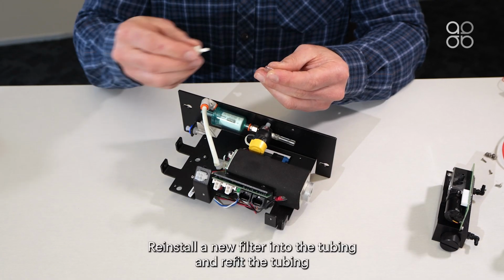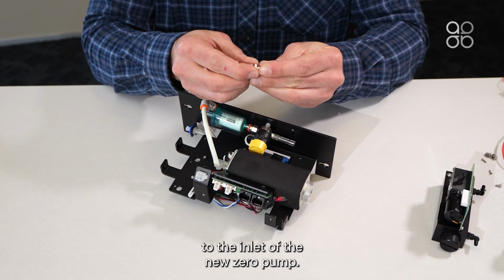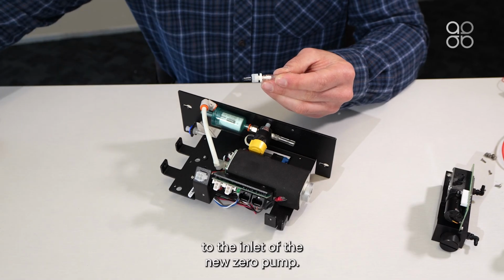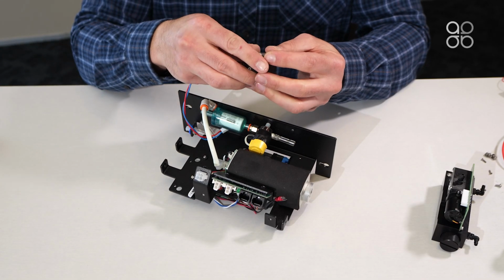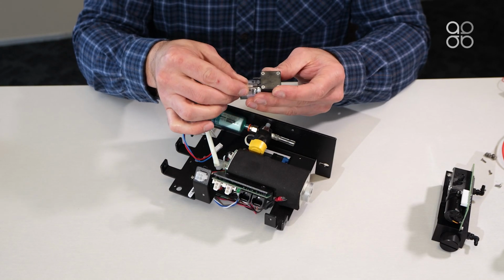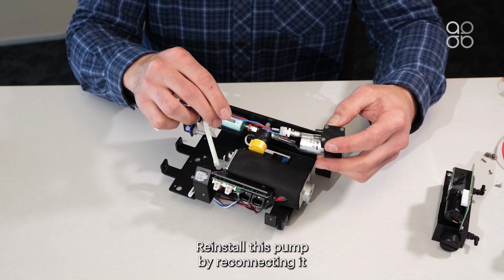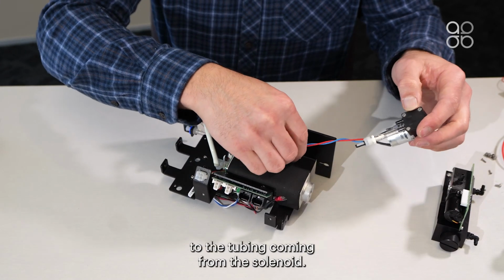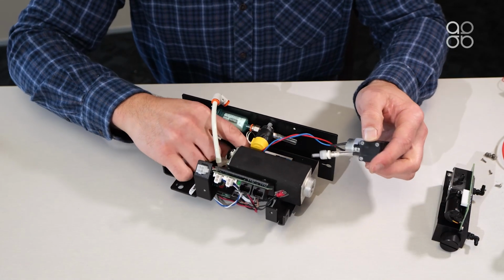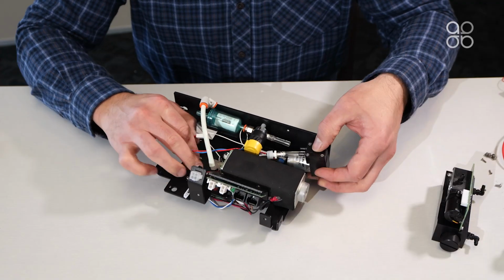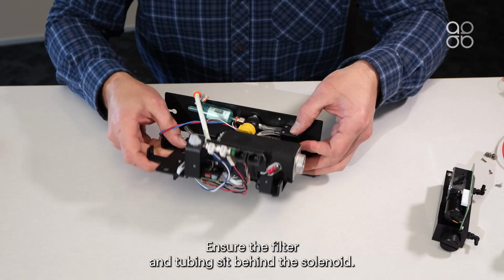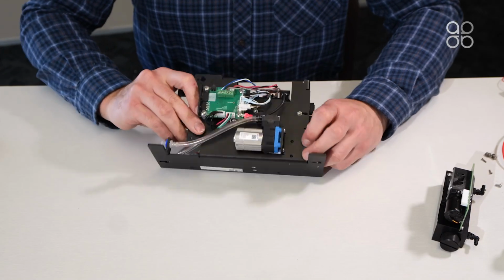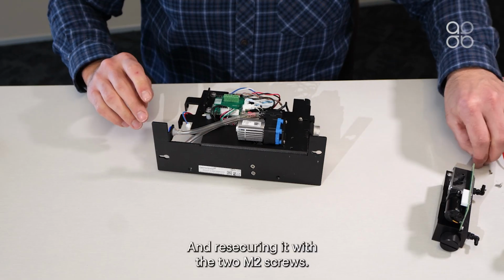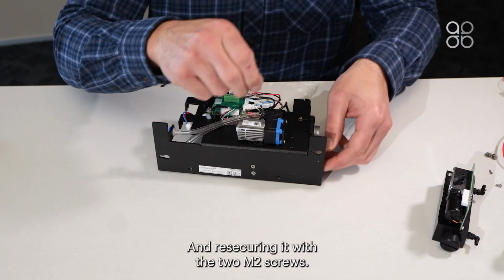Reinstall a new filter into the tubing and refit the tubing to the inlet of the new zero pump. Reinstall this pump by reconnecting it to the tubing coming from the solenoid. Ensure the filter and tubing sit behind the solenoid, and resecuring it with 2 M2 screws.